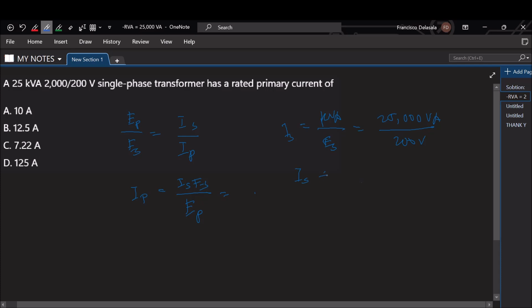Secondary current is just equal to the kVA divided by the secondary voltage, which is 200. Substituting, we have 25 kVA, that is 25,000 VA, divided by 200 volts. 25,000 divided by 200 is equal to 125. So our secondary current is 125 amperes.